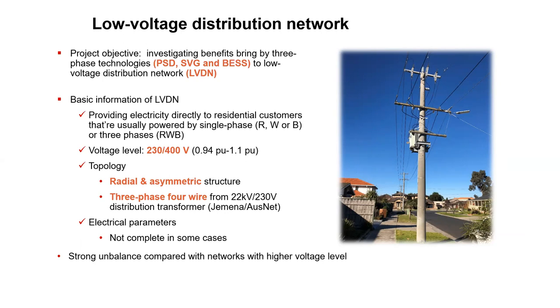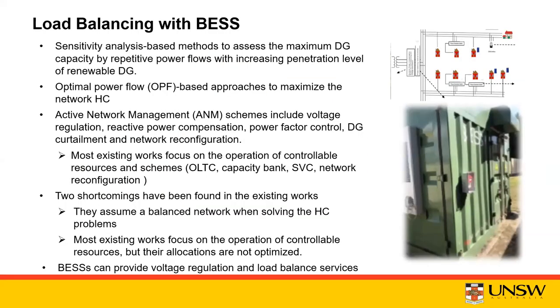A challenge I didn't include in the slide is that many power companies don't have the low voltage, meaning 400 volts or 230 volts level, parameters, conductors, and so on. So even though you can run three-phase power flow, it normally doesn't extend to this low voltage part beyond the 11 kV lines. So from 11 kV down to the 400 volt network, we first had to build a three-phase 400 volt network model, and then analyze the system to get control solutions using grid batteries.